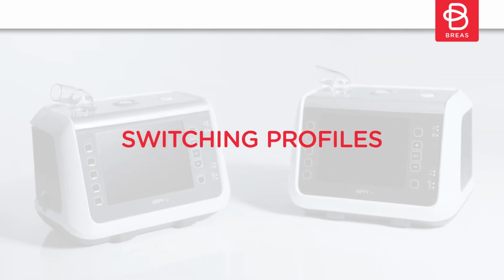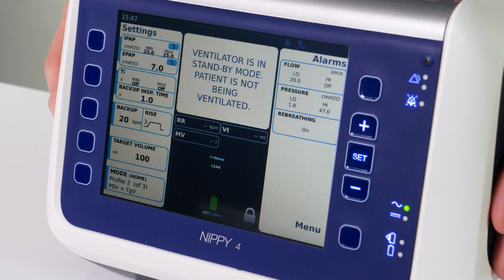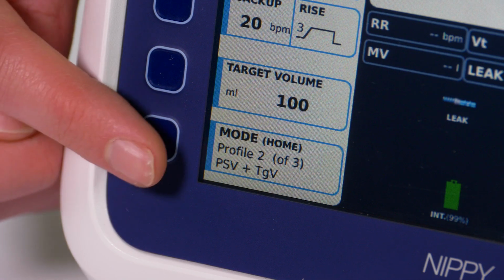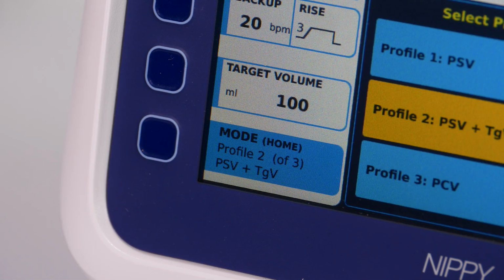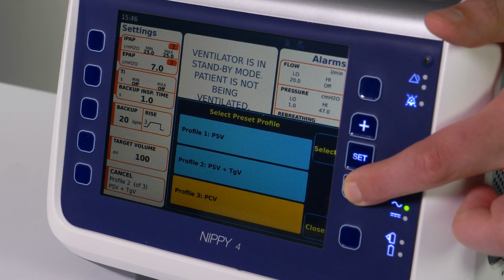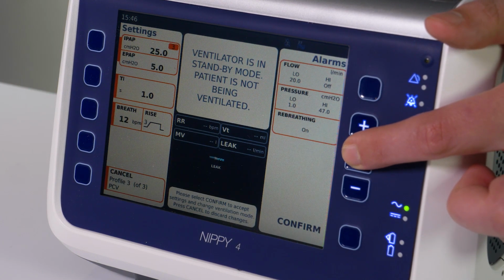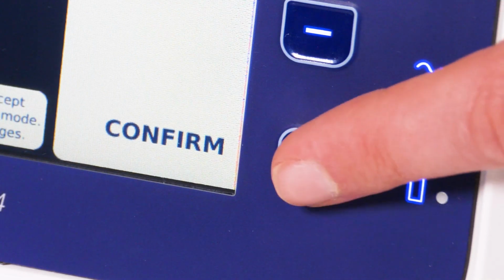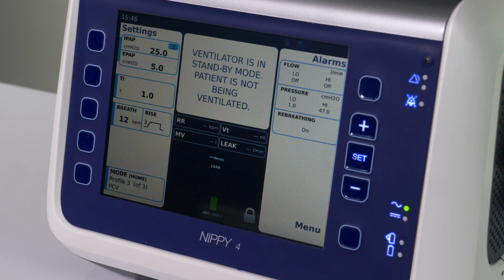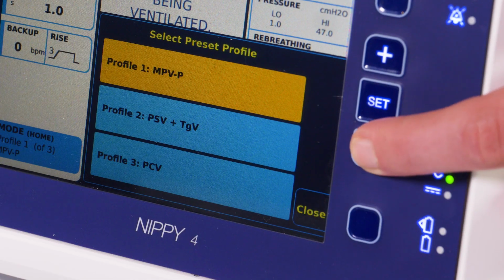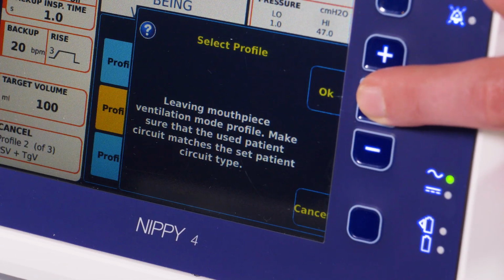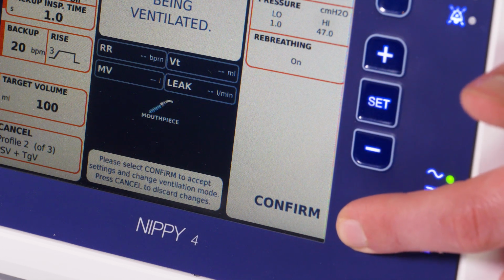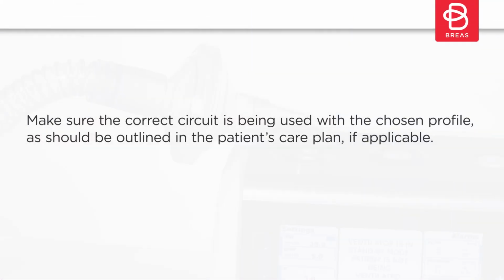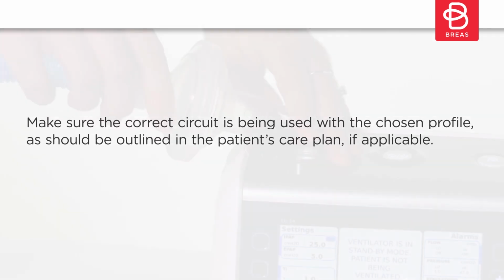Switching profiles. To navigate between the various profiles that have been set up, select the button next to the profile label and use the plus and minus and set buttons to select the desired patient profile. When selecting the chosen profile, the settings will be surrounded by red boxes and you must press Confirm to complete the change. If switching between modes that require different circuits, the device will prompt this on the screen. Make sure the correct circuit is being used with the chosen profile, as should be outlined in the patient's care plan, if applicable.